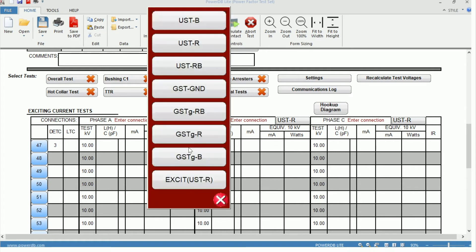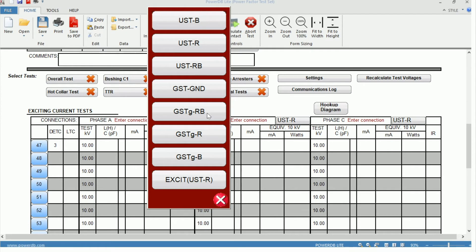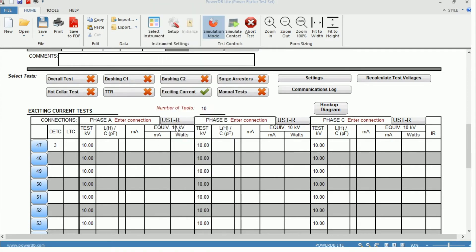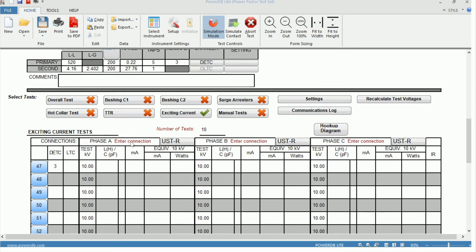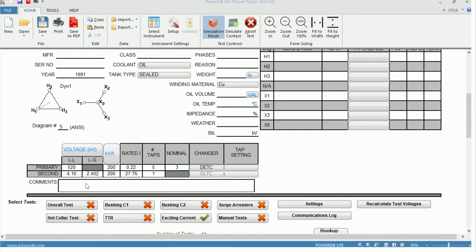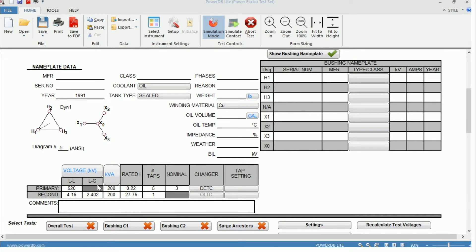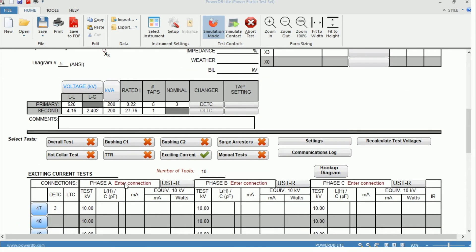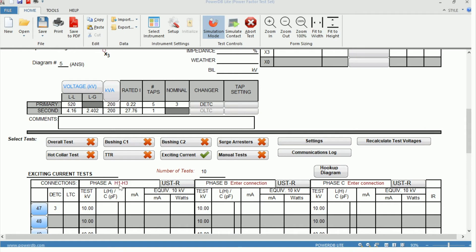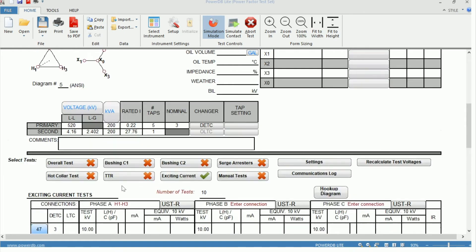And you can change the test mode as well. So we have it in the ungrounded specimen test with the red lead. We can change that to use both red and blue. We can use grounded specimen test, and so on, as you can see here, the whole list. We'll go ahead and keep it on the USTR. And going back to the enter connections, we can see phase A here. So scrolling up, you always need to refer to the vector diagram to determine what the proper bushings are for testing phase. So looking here at phase A, we can see H1 to H3 corresponding to our X1 to X0 for the given vector diagram. So we can type in H1, H3, and that documents that we are attaching the high voltage lead to the H1 bushing and measuring on the H3 bushing when testing the A phase.